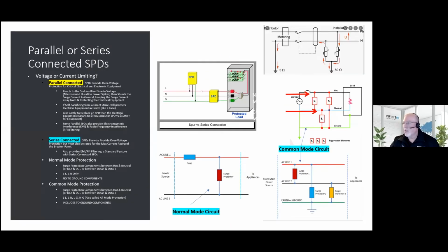Okay, so here we look at the parallel and series connected surge protectors, and what's the difference? Well, a series connected surge protector literally means that the line, the neutral, the ground is coming in and out of it, and then into a breaker. This is equipment, but consider it a breaker, like the main breaker. And so let's say this thing fails and you want to get rid of it, you'd have to shut down the power to the entire building and then remove this device.